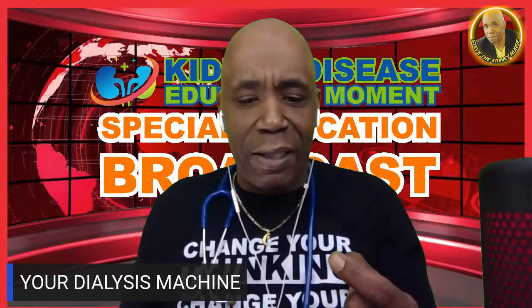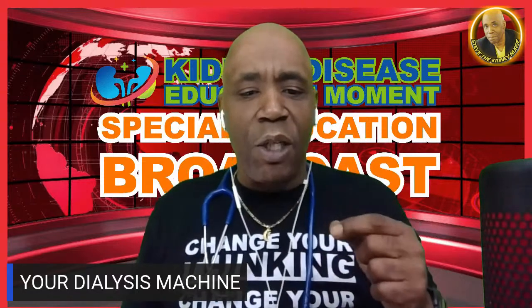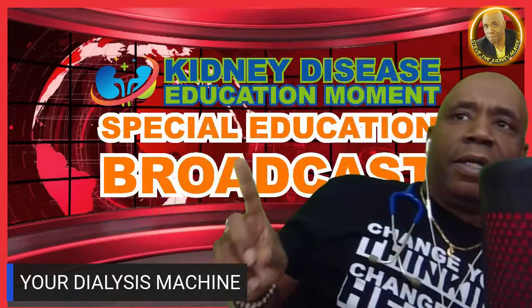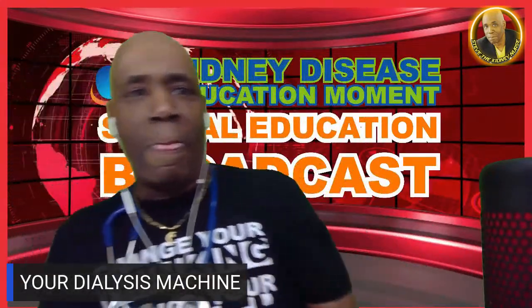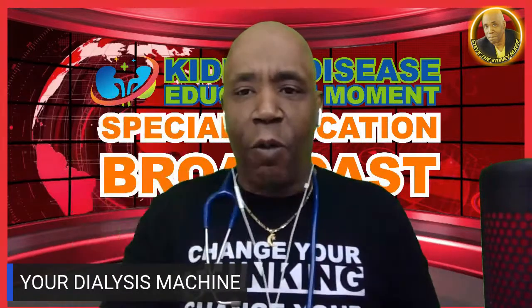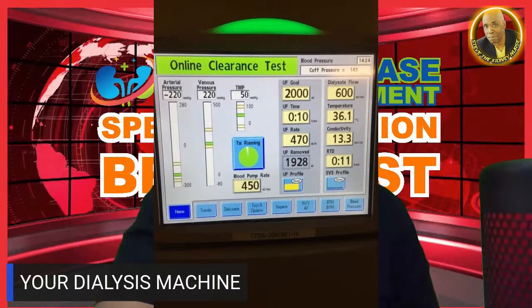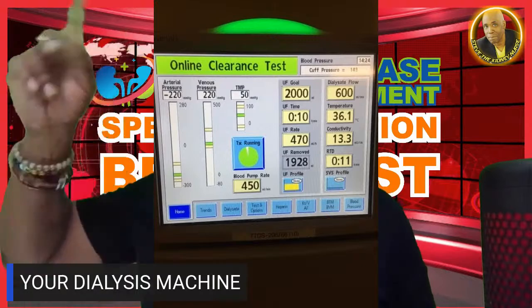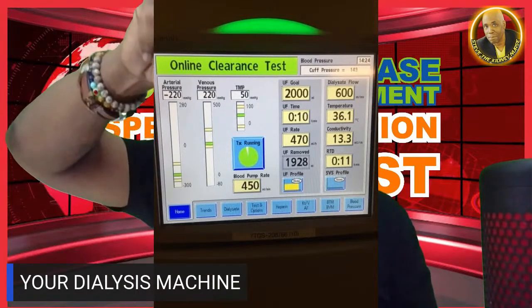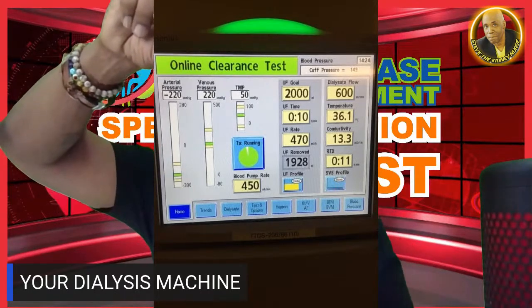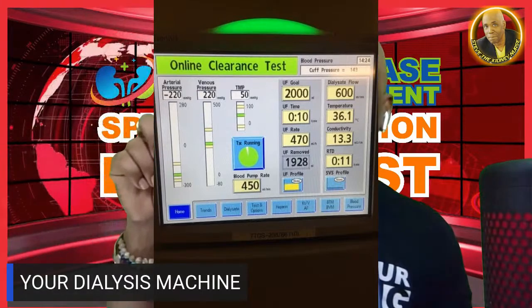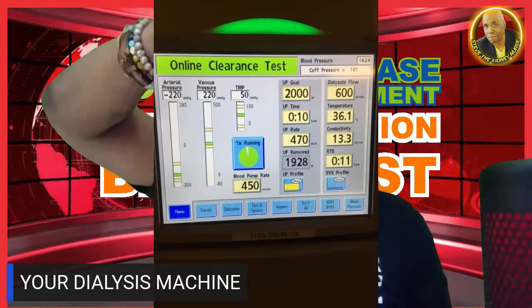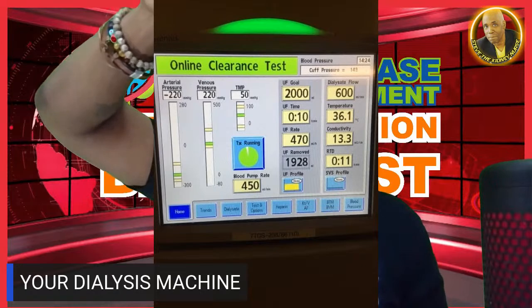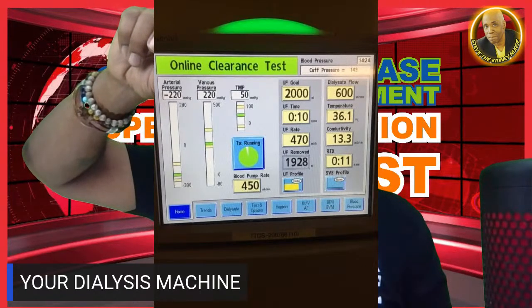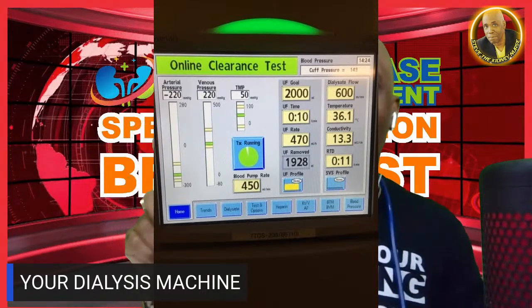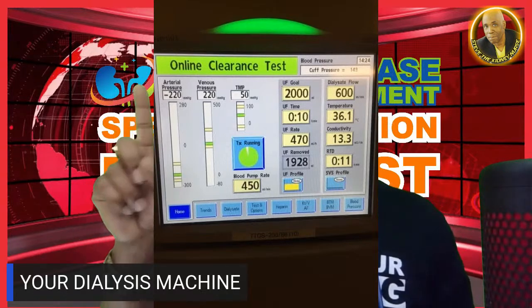Now, the machine checks during this time include checking the blood flow rate, which is right here. I'm sorry, the blood flow rate. The dialysate flow rate. Let me pull it up on the screen. The blood flow rate is right here. The dialysate flow rate is up to the right. The venous pressure. The transmembrane pressure, the TMP. The ultrafiltration rate. The arterial pressure, which you can't see in this picture, but it's right next to the venous pressure. The amount of fluid that has already been taken off. And in this case, it's 1.928.